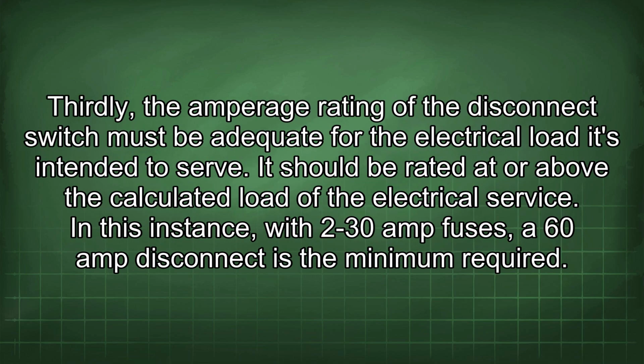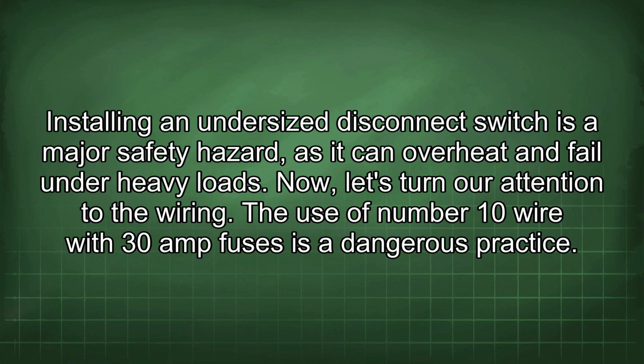Thirdly, the amperage rating of the disconnect switch must be adequate for the electrical load it's intended to serve. It should be rated at or above the calculated load of the electrical service. In this instance, with 2-30 amp fuses, a 60 amp disconnect is the minimum required. Installing an undersized disconnect switch is a major safety hazard, as it can overheat and fail under heavy loads. Now let's turn our attention to the wiring. The use of number 10 wire with 30 amp fuses is a dangerous practice.